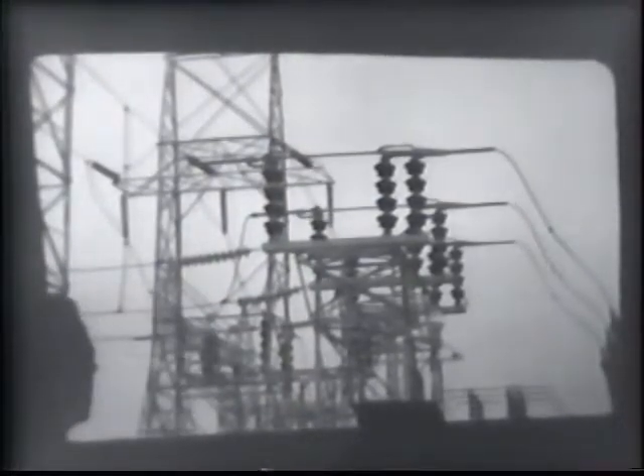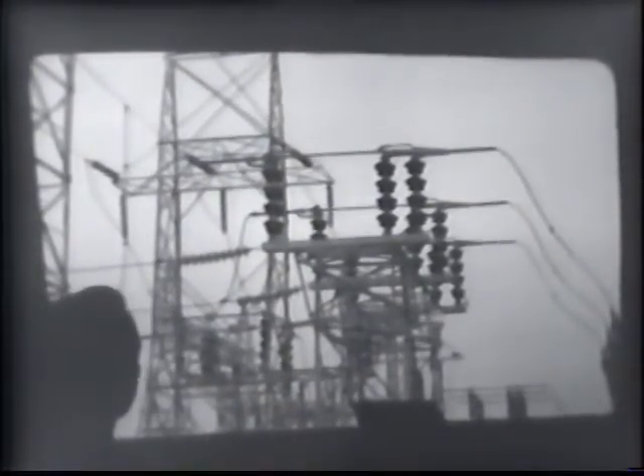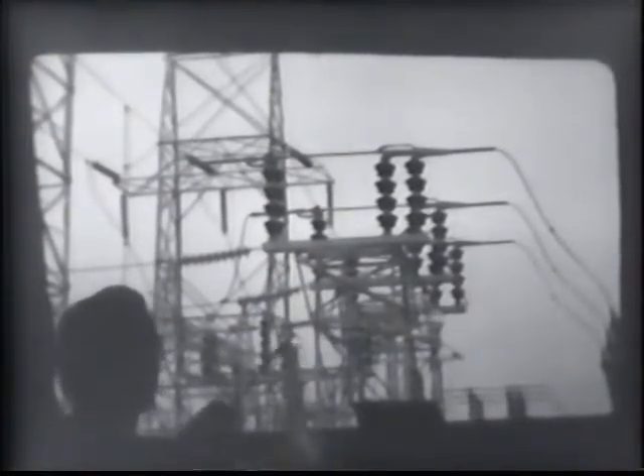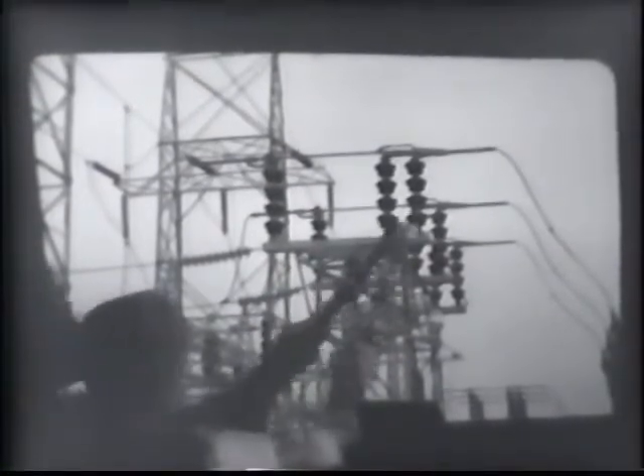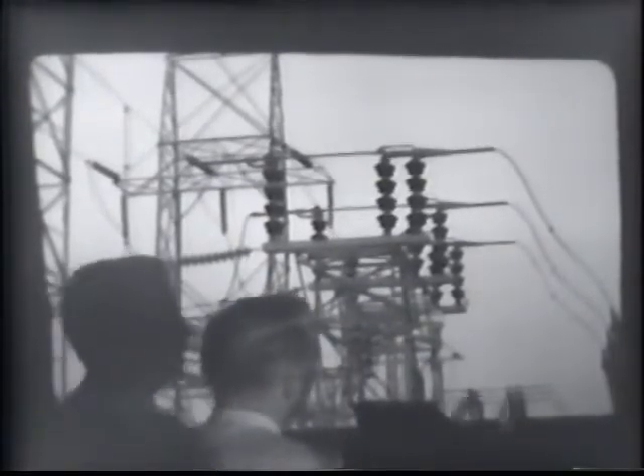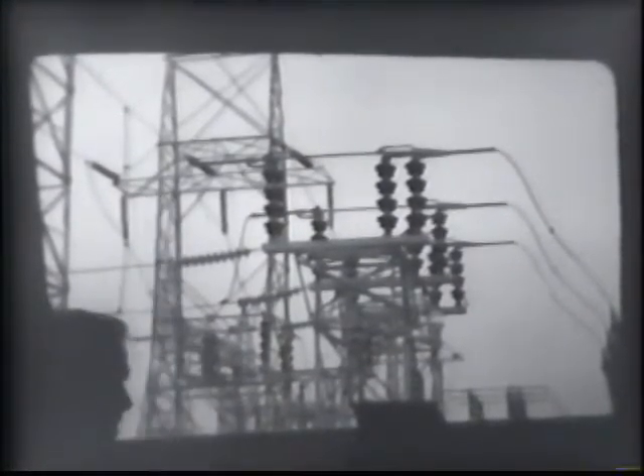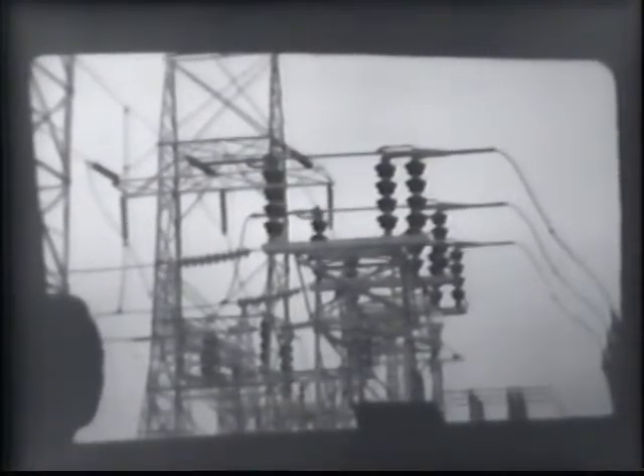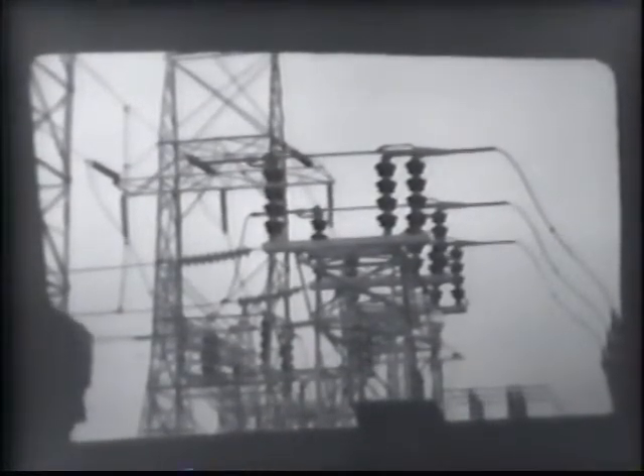And this is another, closer example of the disconnect switch structure, a lace type structure here. At 161 kV, we use 4 pin type insulators. You can just barely see this bundle conductor bus composed of 2 500 MCM conductors with a spacer there. This would be a stud connector there. And I don't know if you can see it, but right along this column here, it looks like there's some step bolts installed so that somebody can climb that column if they had a reason to. Let's see. You can just barely see the shielding conductor coming in there and going out there.